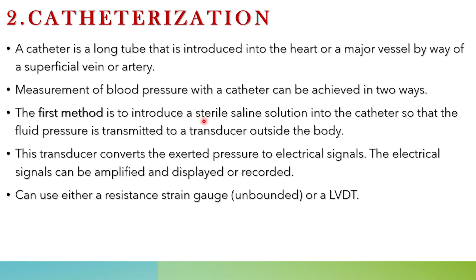In the first method of catheterization, a sterile saline solution is introduced into the catheter, and based on the fluid pressure changes, a transducer outside the body senses the fluid pressure difference and converts that pressure into an electrical signal. The electrical signals can be amplified and displayed or recorded. The transducer used is either a resistance strain gauge unbonded transducer or an LVDT (Linear Variable Differential Transformer).